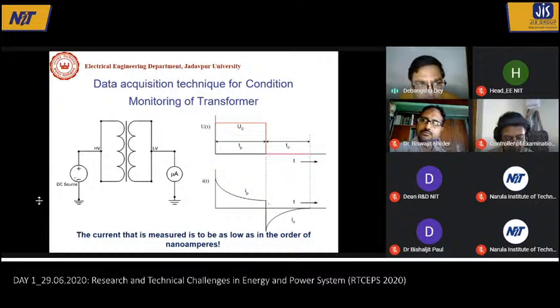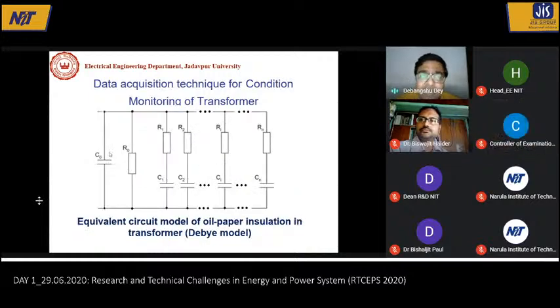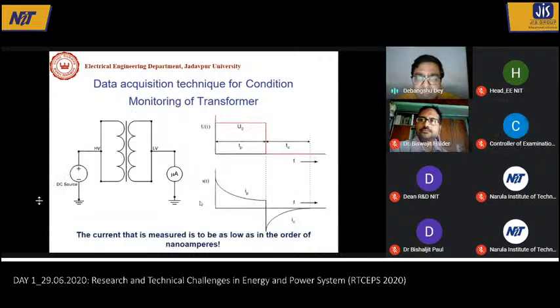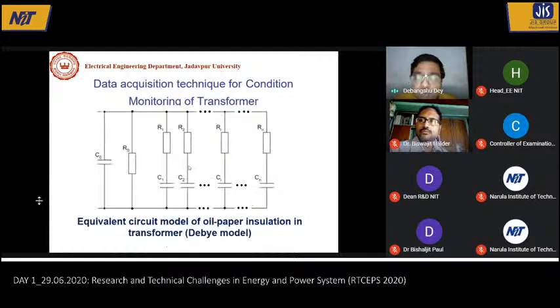When the voltage is shorted, the capacitor formed by the insulation system of the transformer will discharge. From that charging and discharging current, we can build the model, which gives a response similar to this. From this model we can estimate the condition of the insulation by knowing the values of parameters like C0, R0, R1, C1, R2, C2, which can be modeled in different ways.